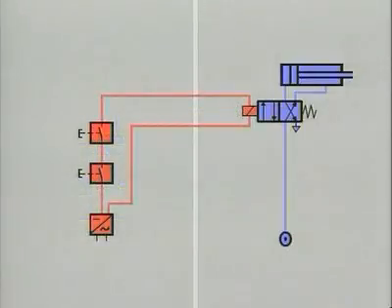actuated. In a corresponding electro-pneumatic control, there are electrical signal elements in the control part. In this case, signal processing is not carried out by a special device, but by connection of the various signal elements in such a way as to produce the function. The directional control valve, or more accurately, the solenoid valve, is now actuated electrically.